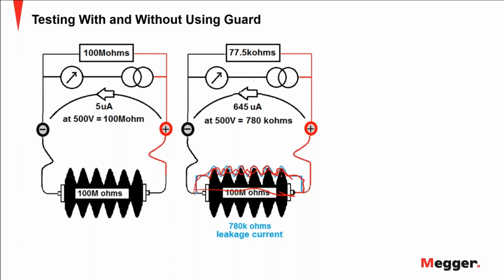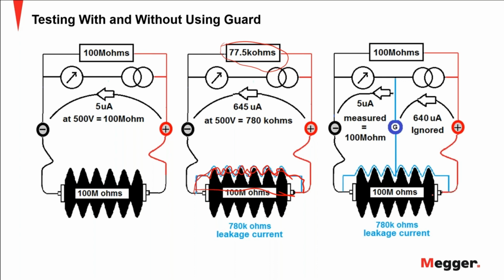So now I have the current due to the resistance plus the current due to the surface. And now I know that my resistance is good, but I'm getting a result of 77.5 kilohms. So that is not a good result. But if I use the guard terminal, the guard conductor, this current gets deviated, and now I'm only measuring the current that I'm interested in, which is the current circulating through the insulation.